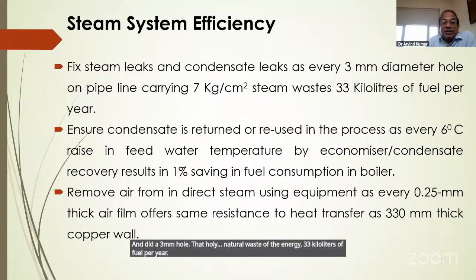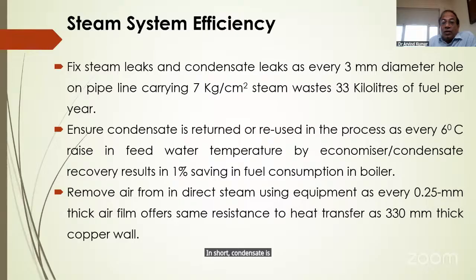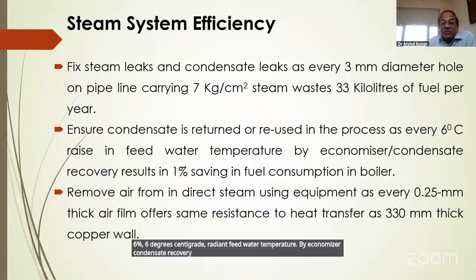Ensure condensate is returned to and reused in the process, as every 6 degrees centigrade rise in feed water temperature by economizer condensate recovery results in 1% saving in fuel consumption in the boiler.